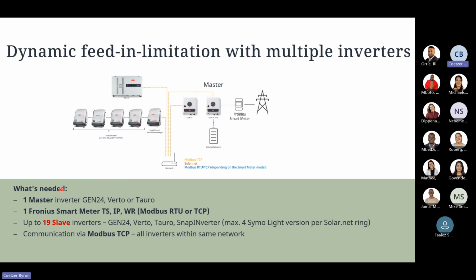With one master assigned, again either the Gen 24, Verto or Tauro, we will then make sure that we have one Fronius smart meter connected. Again, this can either be the TS, IP, or WR, using either Modbus RTU or TCP comms directly to the router or directly to the inverter. And this will allow us to control up to 19 slave inverters in the configuration.